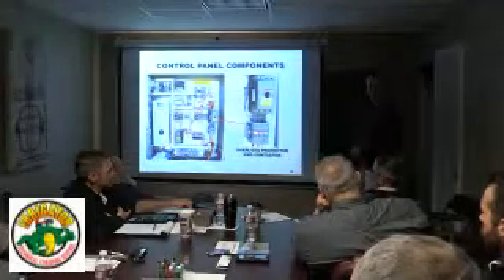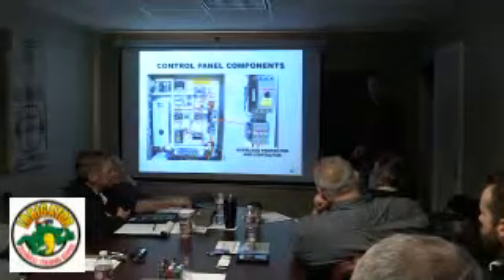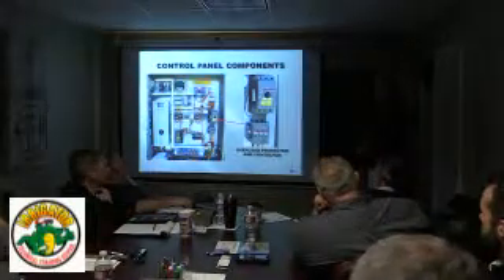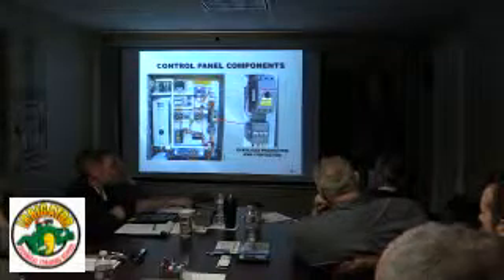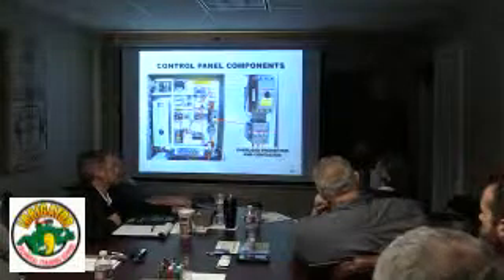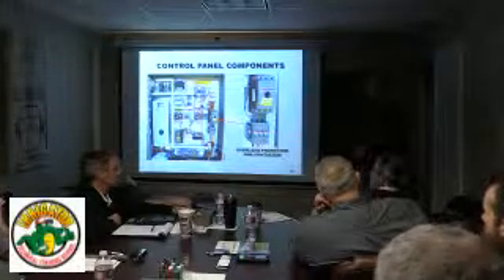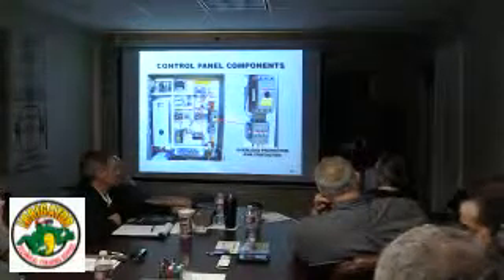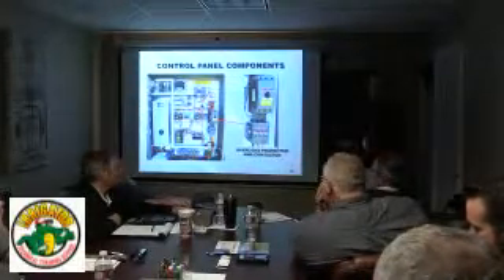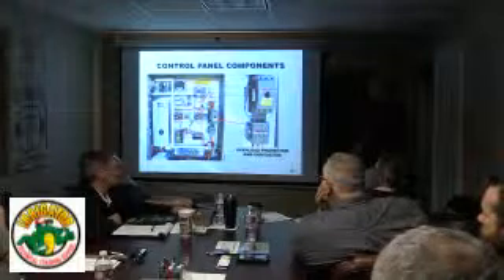Basically, a second safety. The drive does its own checks, but who's going to respond faster, the drive or that unit? Probably the drive, most of the time. So it's just a double safety. However, the drive will stay running on single phase power up to a certain amperage. If it's only running at 50 hertz and you lose a phase, the drive may continue to run, but the motor's voltage monitor is going to shut it down right away, because it senses the loss of phase.